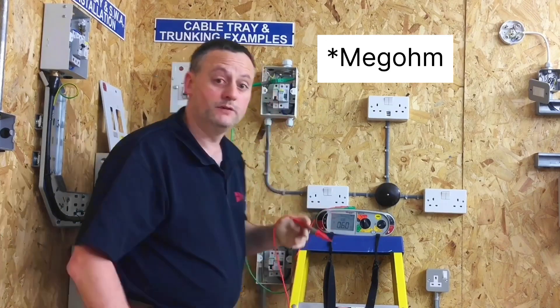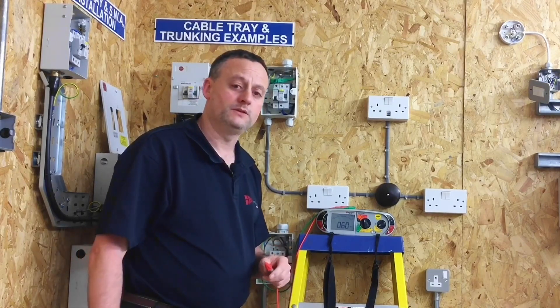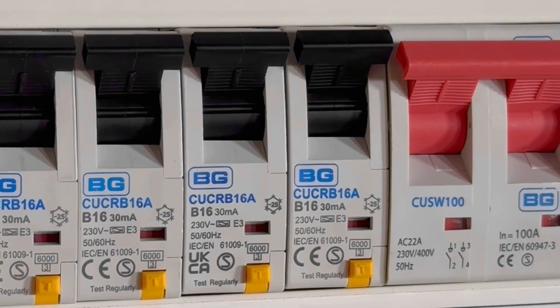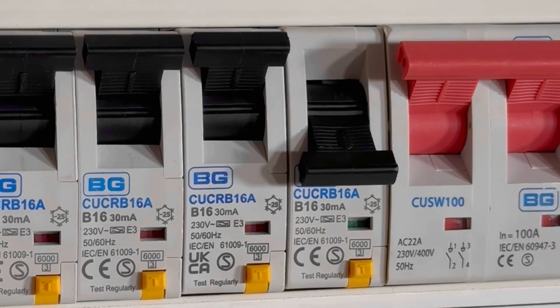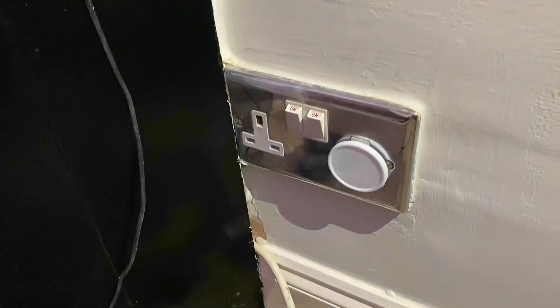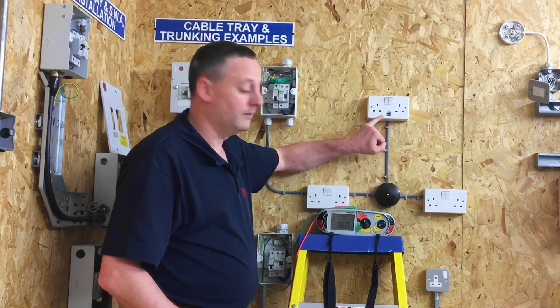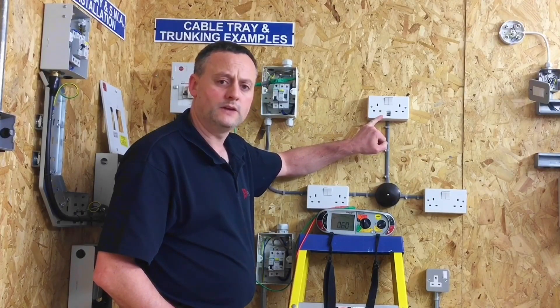What we have proved is that there isn't a dead short — we haven't got zero — so when the circuit was energised it wouldn't disconnect the overcurrent protection device, but there is something in circuit. On an inspection we need to investigate and find out what's been left connected. It could be something plugged in, but here all socket outlet items were removed and what we have is a permanently connected USB socket outlet.